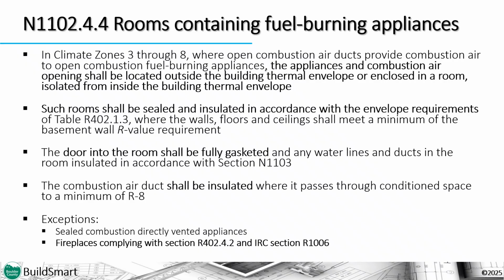This will ensure that outdoor combustion air that is needed for the atmospherically vented appliance does not interact with the conditioned air inside the building thermal envelope. In reality, this is a very difficult detail to comply with, so it is better to ensure that if you are installing gas-fired mechanical equipment, that you always install sealed combustion equipment.